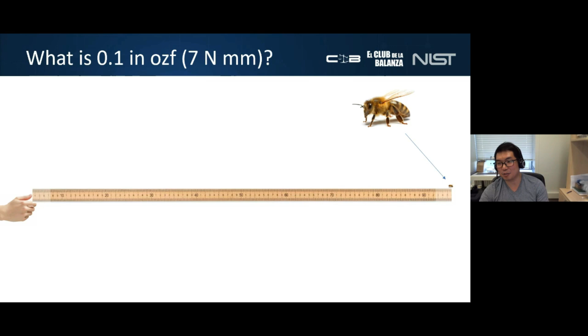Currently there are two main testing or calibration processes for torque tools. The first method is for mid and high ranges, where a torque tool such as a torque wrench is set to the desired torque value and oriented so its drive end interacts with a torque transducer, which typically contains a couple of calibrated strain gauges internally. Then either the transducer or the torque tool is rotated until the tool clicks. This click is detected by the measurement system, and the torque measured by the transducer is displayed.